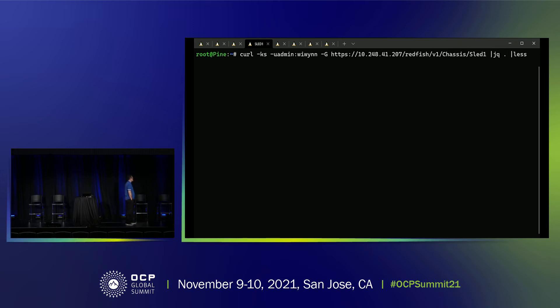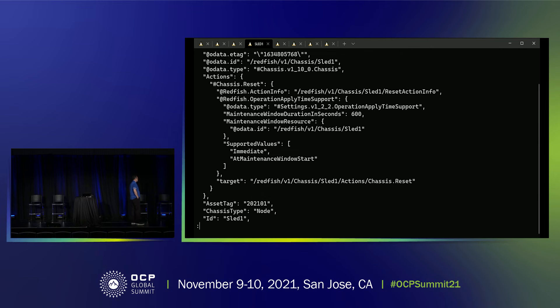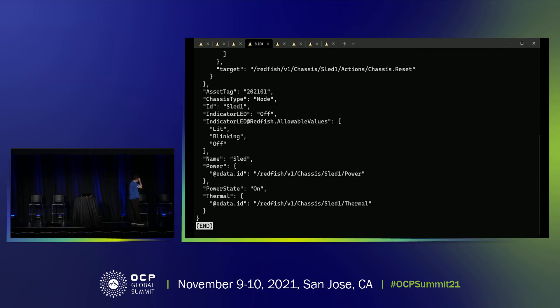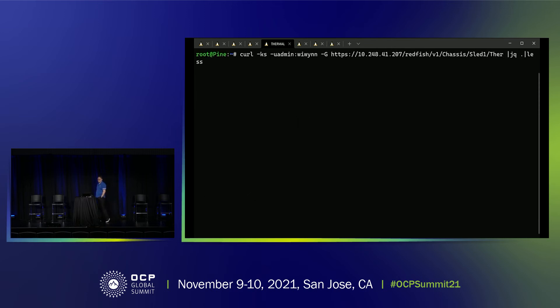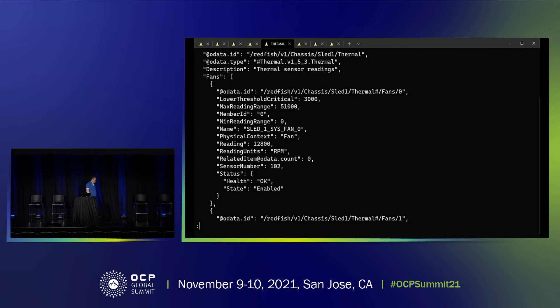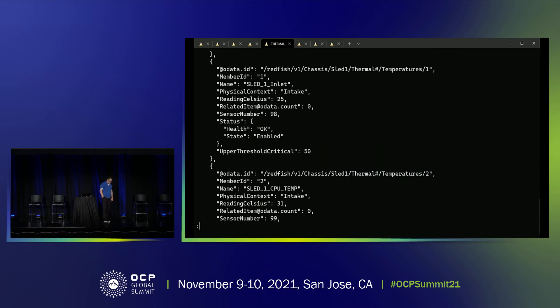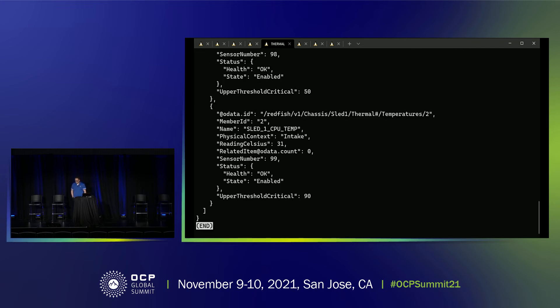There are four chassis sleds on EP100. We can check each sled's status via the sled API to get chassis sled info. Sled info includes sled ID, asset tag, LED status, and power state. It also lists sled sensor APIs like power and thermal API. We can get thermal-related sensors through the sled thermal API, which shows fan sensor name, fan speed reading, inlet and outlet temperature sensors, and CPU temperature sensor.